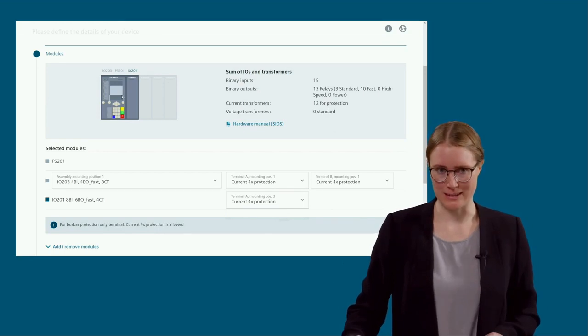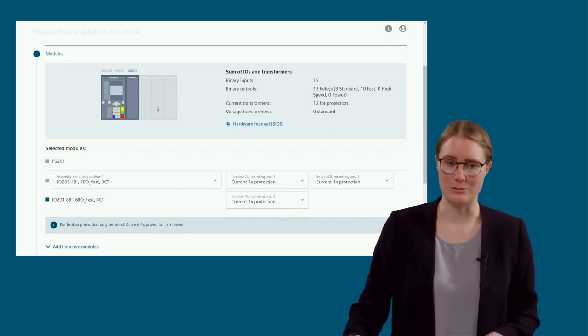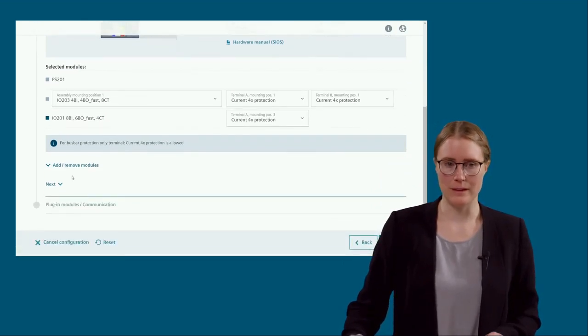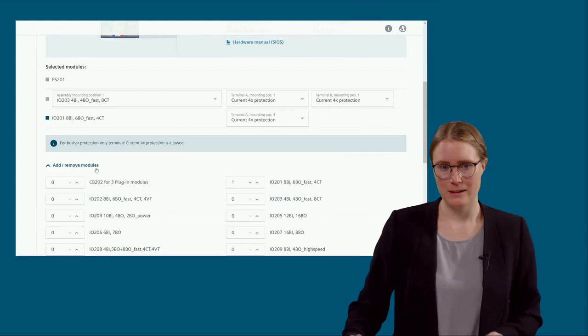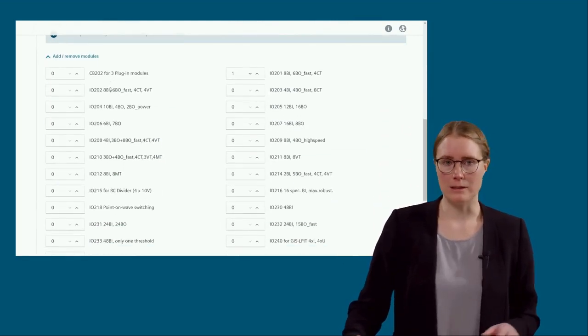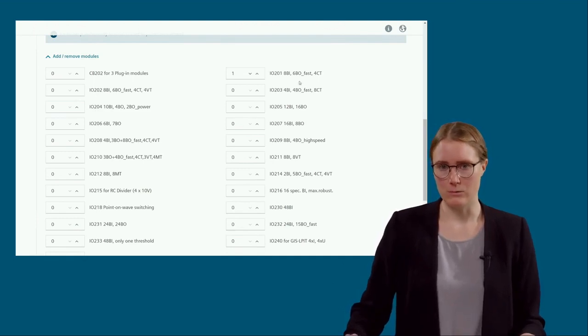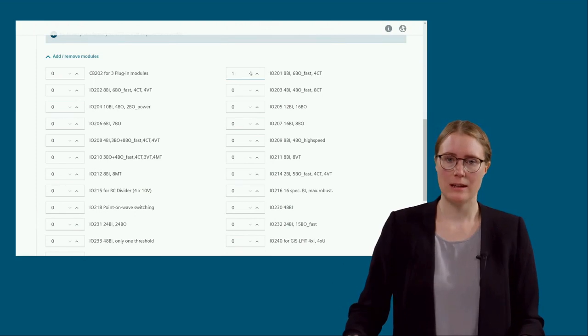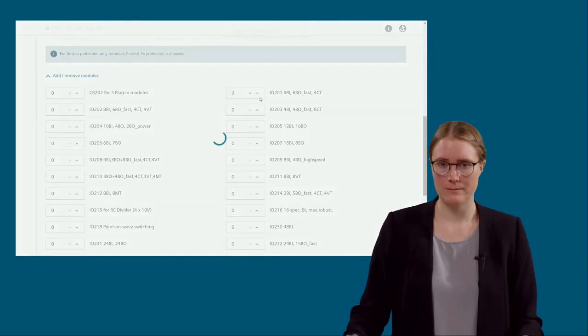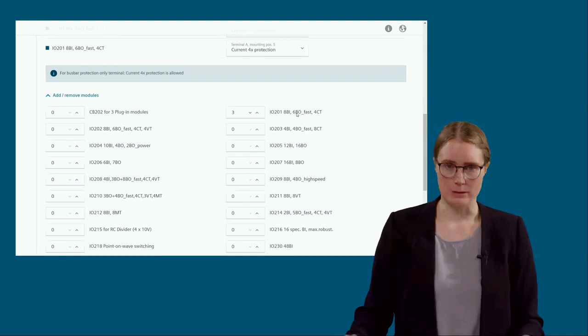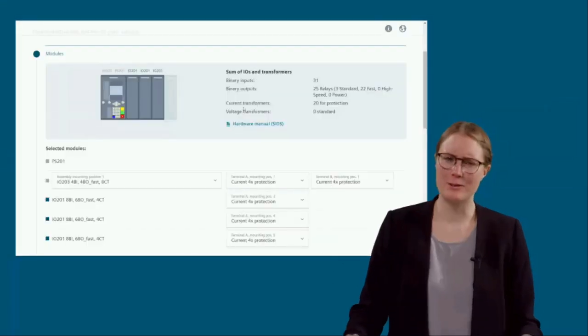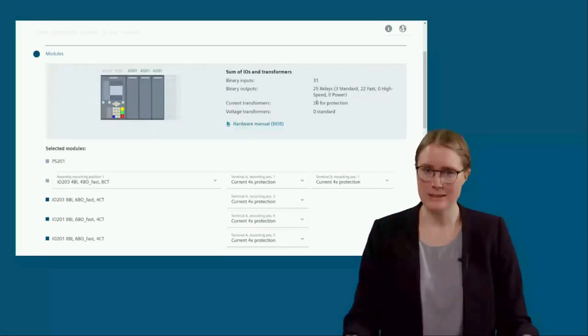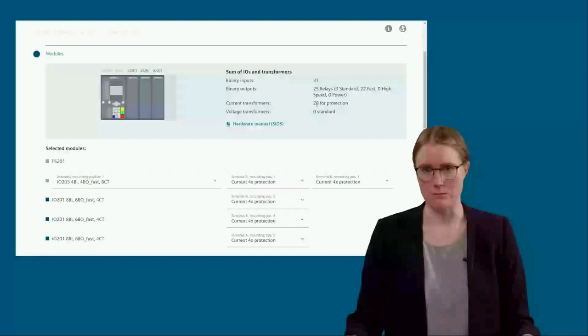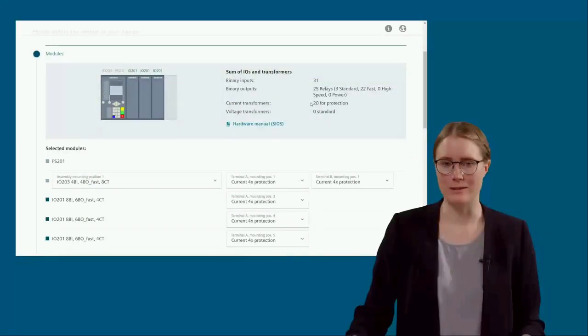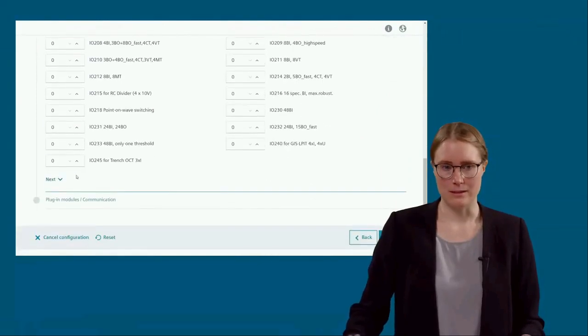So I need more of these IO201 expansion modules. This is possible to add at this step here. Here's an overview of all the possible extension modules that are available. One IO201 is already selected, and I now increase the number up to 3 for our configuration. Now we can double check if this is enough. And now we see for the current transformers, we have 28 now, and this is sufficient for the configuration we want to do now. Okay, so get to the next step.